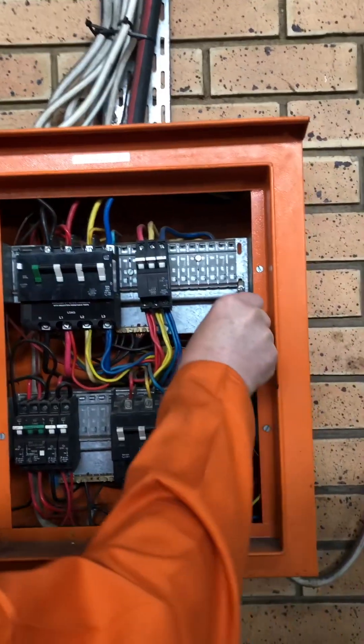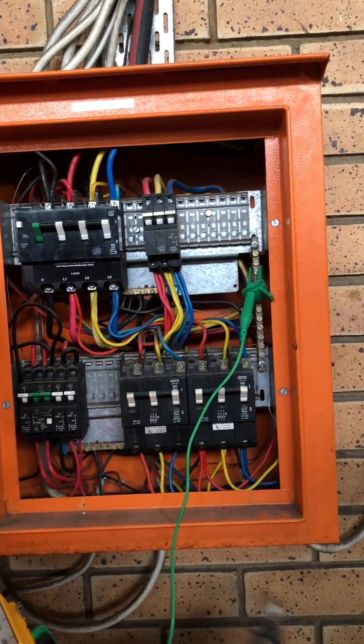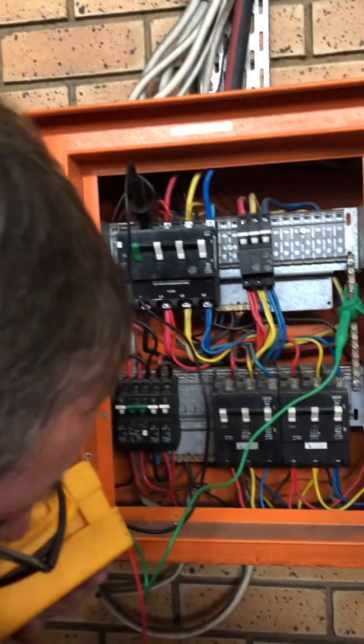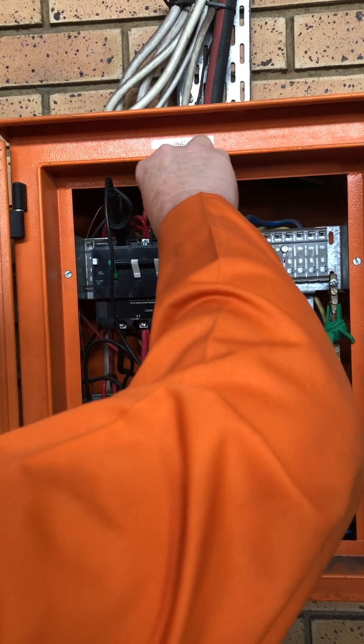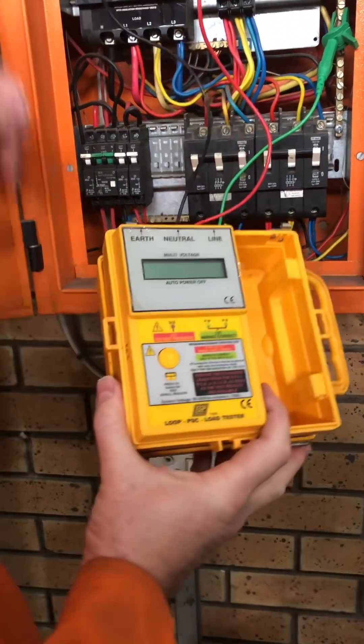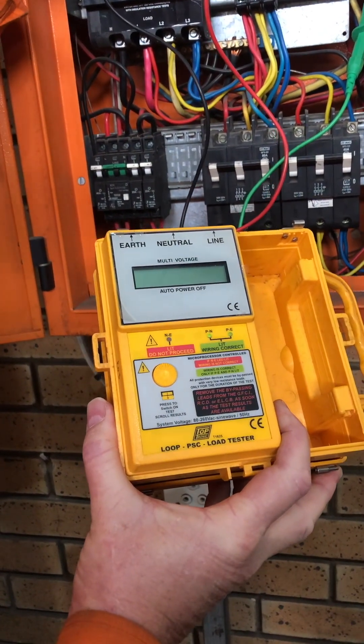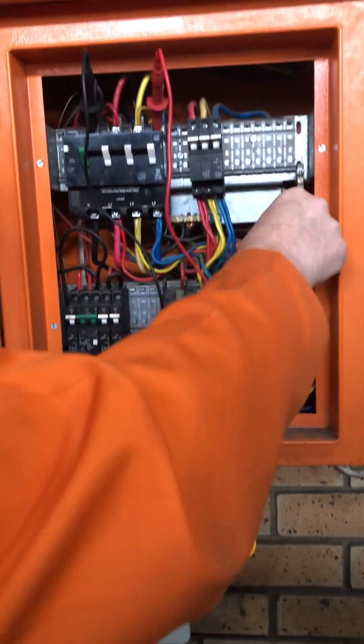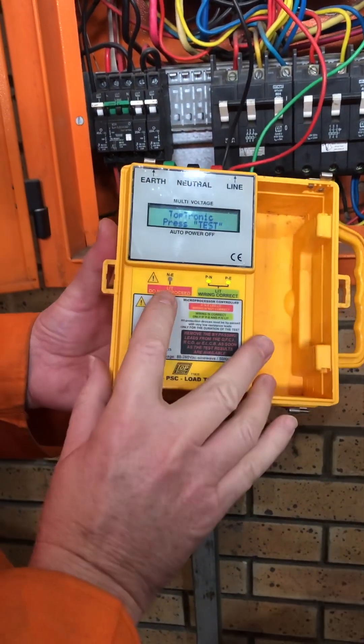So you put your earth first, then you put your neutral, and then you put your live. You can put your live on anyone you can get to. You see there it's showing me it is correct. As soon as it's not connected correctly, you will get a red light which says do not proceed. So make sure they are quite tight — they won't just jump off. Then you press a button, switch on, and now it says press test.